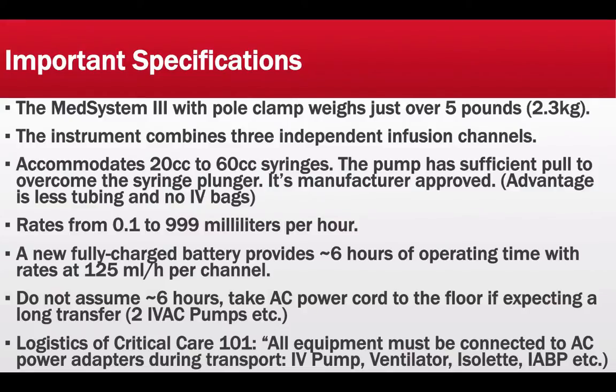So this is just a summation of all the important specifications that were shown in the previous slides. The MedSystem 3 with the pole clamp weighs just over 5 pounds or 2.3 kilos. The instrument combines 3 independent infusion channels, so each channel could facilitate its own rate. It accommodates 20 to 60 cc syringes, and the manual states it's either BD brand name or a monojet. The pump has sufficient pull to overcome the syringe plunger, so do not worry that the plunger will not advance.